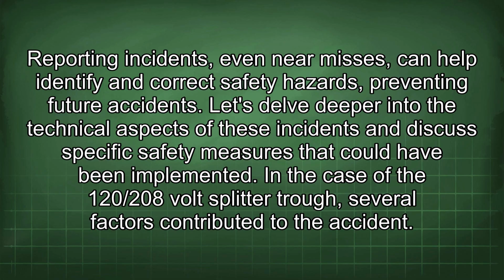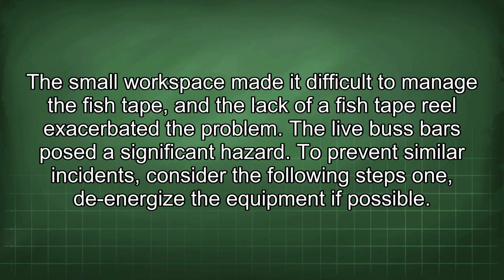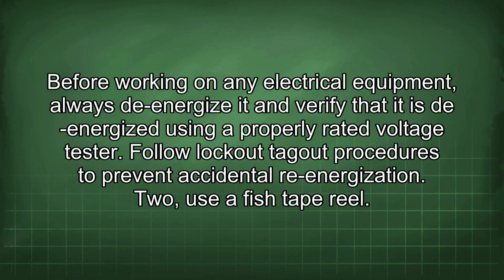120/208 volt splitter trough, several factors contributed to the accident. The small workspace made it difficult to manage the fish tape, and the lack of a fish tape reel exacerbated the problem. The live bus bars posed a significant hazard. To prevent similar incidents, consider the following steps. 1. De-energize the equipment if possible. Before working on any electrical equipment, always de-energize it and verify that it is de-energized using a properly rated voltage tester. Follow lockout-tagout procedures to prevent accidental re-energization.